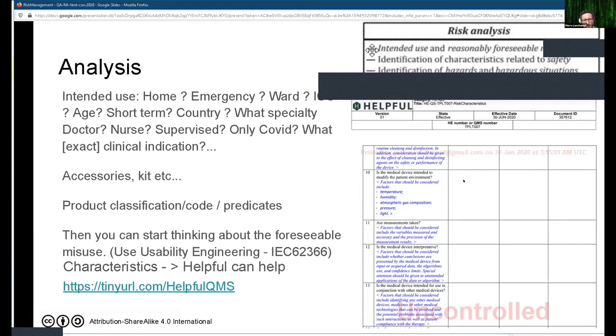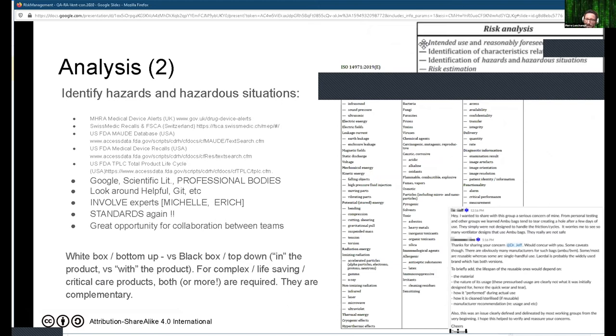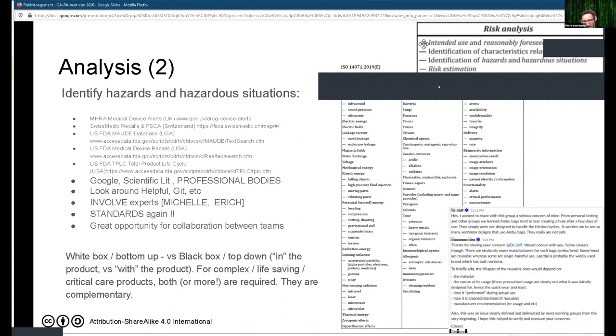There are a lot of other resources — including incident databases that we typically use in industry to get inspiration on risks and hazards. You can look at professional body publications and involve experts. You want to do this according to both a bottom-up and a top-down approach — looking at the product as a black box, or doing an FMEA looking at all the components. The standard itself gives you checklists and lists of fields to examine your product under, including energy and materials.